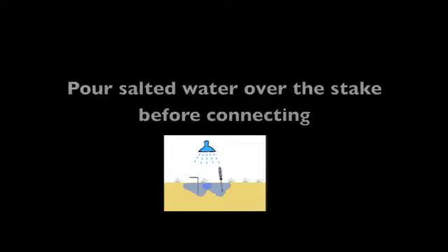To improve the ground connection, you can try these strategies. Ensure the connection point on the stake is not rusted. Embed a longer stake deeper into the ground to reach wetter ground. Pour a gallon of salted water over the stake before connecting.